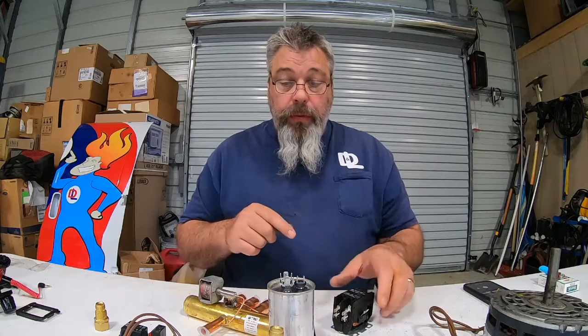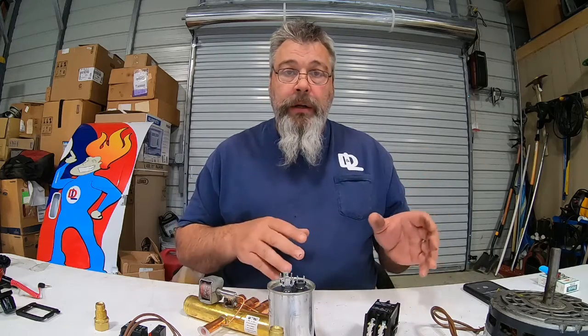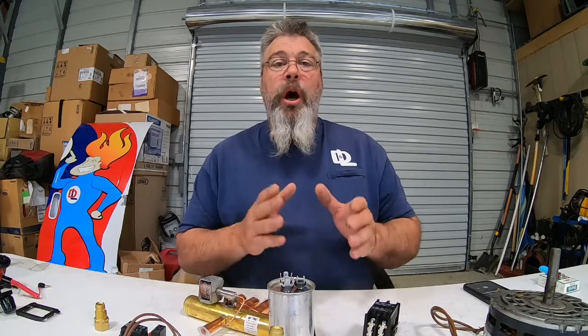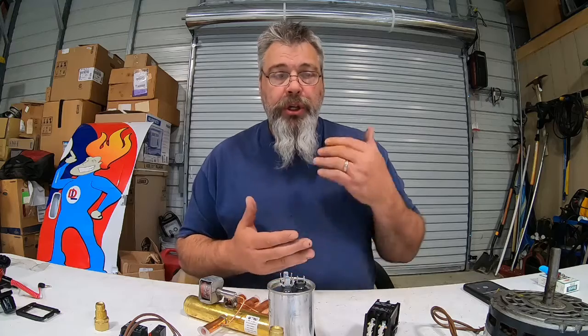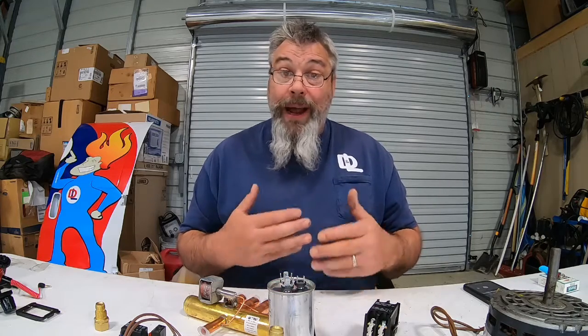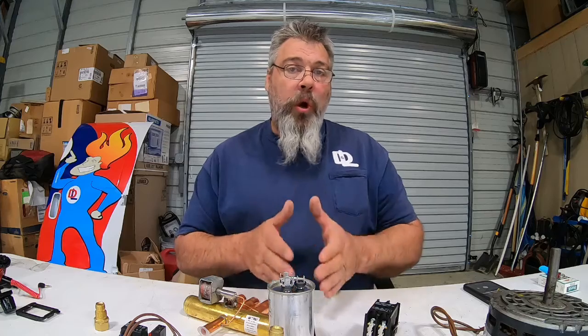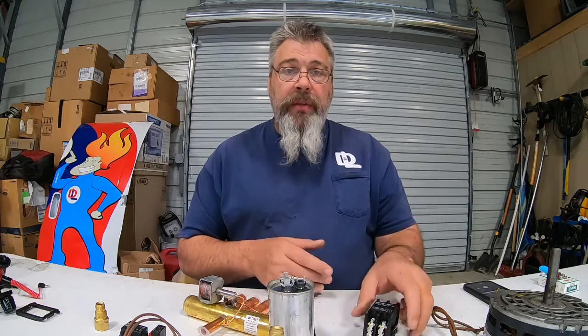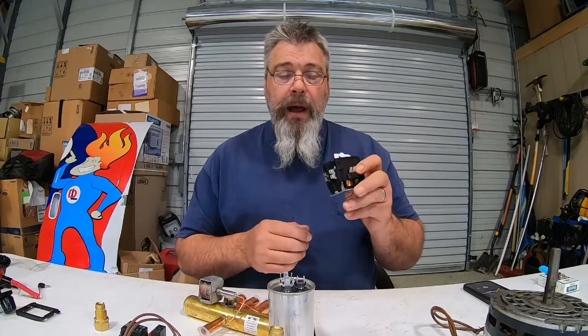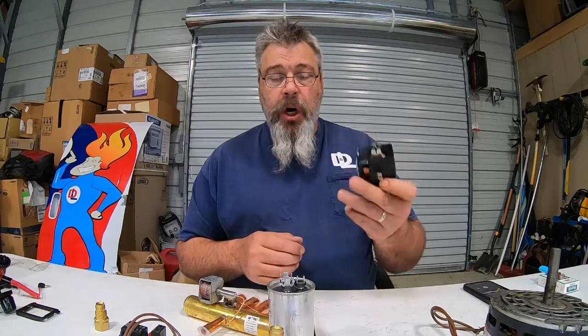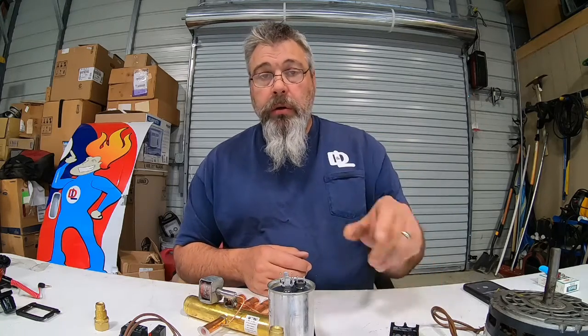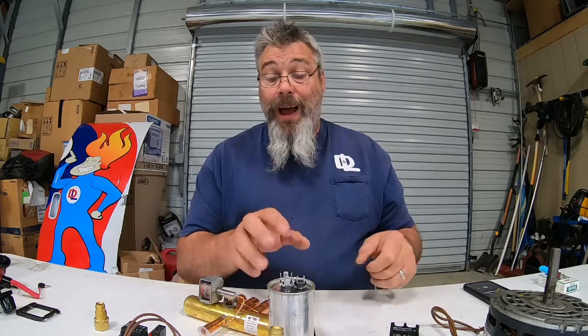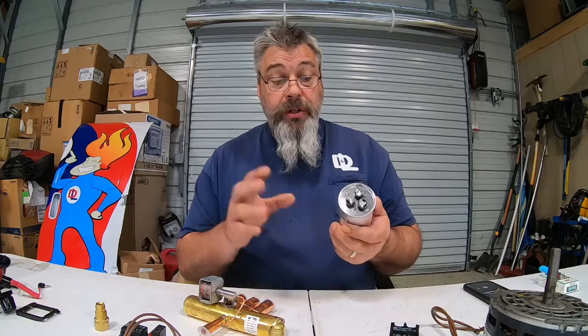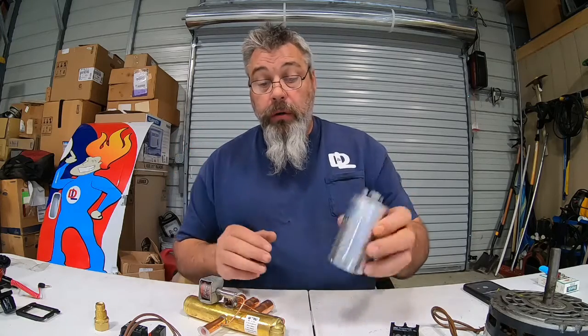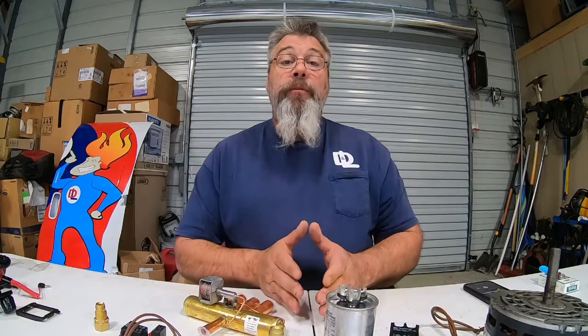What I do want to tell you is some of these components need to be maintained. You need to have them checked out periodically. I'm not saying you have to do it every month, but do it periodically. We prefer, and I highly recommend, a maintenance contract either with D&L or with somebody else, that they come out twice a year and look at it, because you're going to prevent these simple contactors from going bad, or replace them before the summertime hits and it's 100 degrees outside and you're trying to find a service technician, or one of your components is getting ready to die. Your capacitor is very, very weak because it has stored so much energy in it that you want to make sure that it stays up and running to where you need it to be.